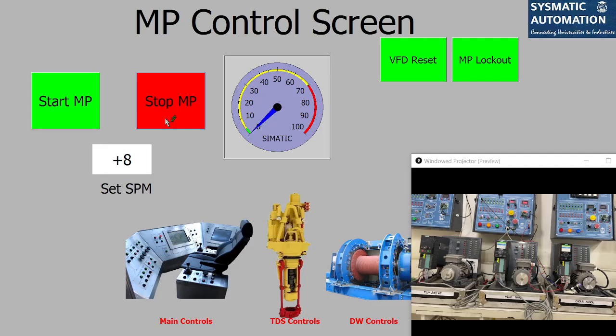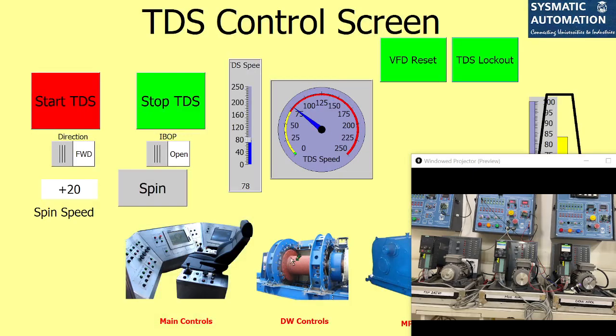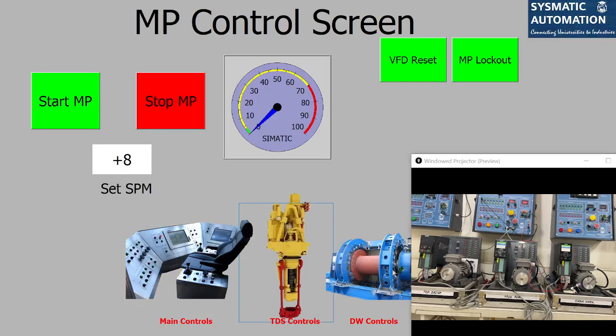So here I will stop it. There is one more interlock for the mud pump. For example, my top drive IBOP is closed. It was open before. Now I close the IBOP, then I go to the mud pump and keep this, although it is 0. Now if I try to start my mud pump, it comes with a new fault. It says IBOP closed, so it will not allow me to start my mud pump.